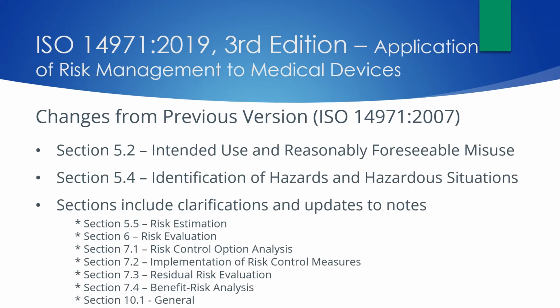Section 5.2, the intended use and reasonably foreseeable misuse, has a clarification of the requirement to document reasonably foreseeable misuse. This goes beyond user error, requiring manufacturers to consider a broader range of risks. For example, orthopedic manufacturers developing smart implants must consider the cybersecurity implications of connected devices in patients. Anything with embedded software must be robust and secure, where reasonably foreseeable misuse can result in high impact risks.